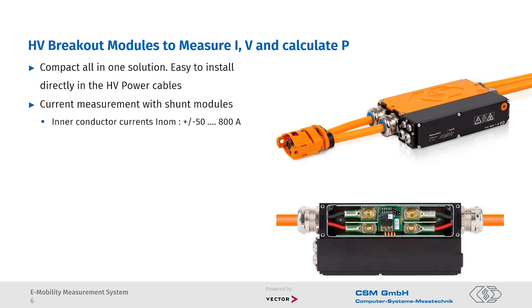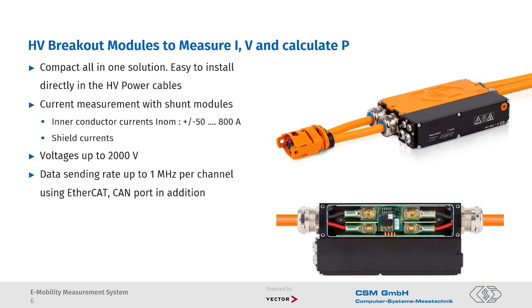We can measure currents up to 800 amps nominal inner conductor currents, and also we can measure the shield currents. We can measure voltages up to 2000 volts, and this really high speed, with data sending rates up to 1 MHz per channel using EtherCAT. At the same time, data is sent via CAN at lower speed. The reason for this is to use CAN for data reduction in long-term applications, where high speed is not necessary. But if it is necessary, it is available.